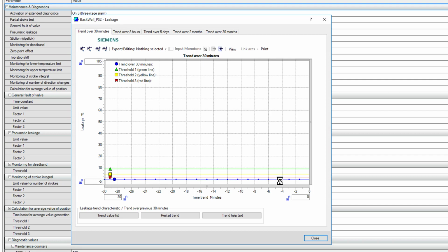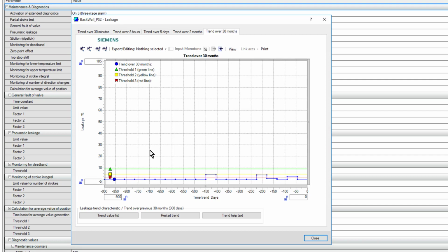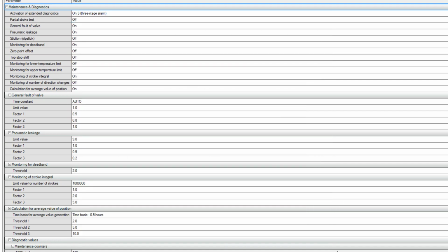And we're not actually looking at the other side effects. Could be a breakdown in the quality of the product that you're making. But again, I can see here over 30 days that I've had some leakage alarm issues. And if I was to overlay those with my control deviation, I wouldn't be surprised that those two coincide. We need to automate this data collection, and that's what digitalization is all about.